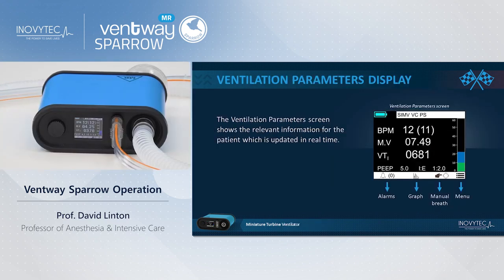You will see on the screen now the ventilator parameters display. You will see the breaths per minute rate, which is preset by default in the ventilator, the selected tidal volume, which will be the tidal volume in mandatory ventilation, and if the patient takes a spontaneous breath, what the tidal volume is in spontaneous ventilation, and you will see the resultant calculation of the delivered minute ventilation.